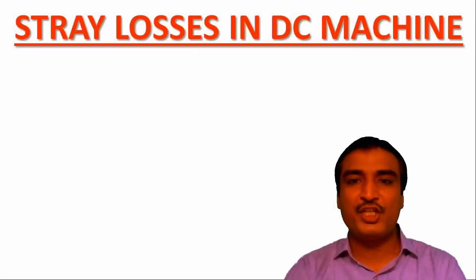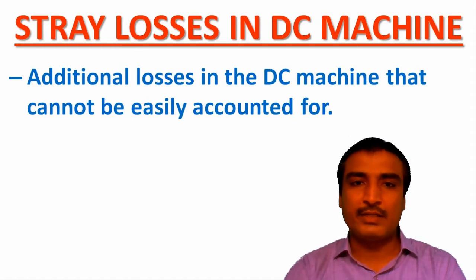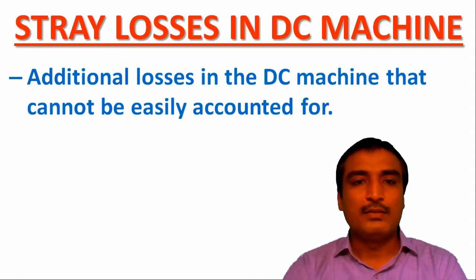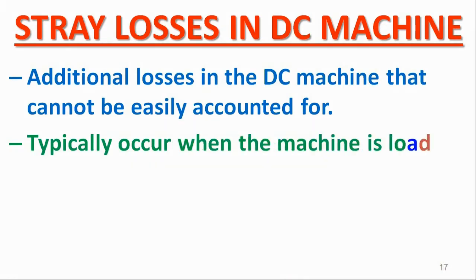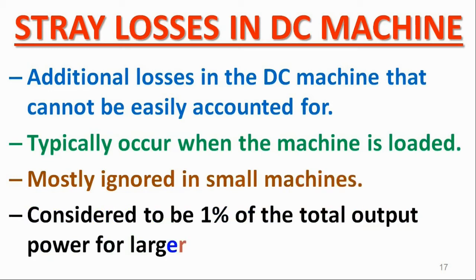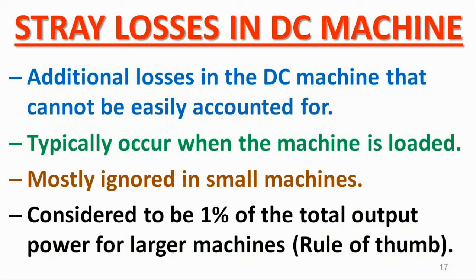Stray losses in DC machines: There are some additional losses in the DC machine that cannot be easily accounted for. Such losses are termed as stray losses. The stray losses typically occur in the machine when it is loaded. In small machines, the stray losses are mostly ignored. However, for large machines, the stray losses are generally considered to be 1% of the output power in total.